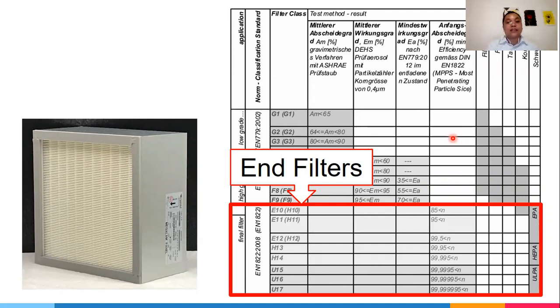As long as the pressure drop requirement of your end filters is included in your calculation, it doesn't really matter where you put them, except that it matters that they go after the fan. They shouldn't come before the pre-filter, or your end filters will become useless. After the big particles and smaller particles are captured, that's when you place your end filters, whether immediately after the fan or at the terminal unit, as long as it's after the fan.